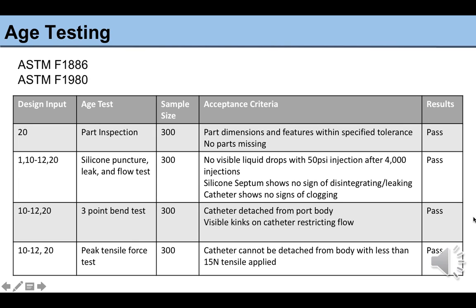For age testing, we followed ASTM F1886 and F1980, which is for visual inspection and accelerated age testing. For accelerated age testing, we looked at the triport assemblies that were manufactured in the manufacturing procedure and placed them in an environmental chamber set to 55 degrees Celsius and 20% relative humidity for a total of 20 days. After the 20 days, the triport was visually inspected and tested as specified in the DV protocol.